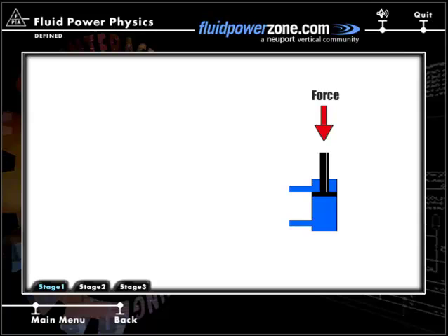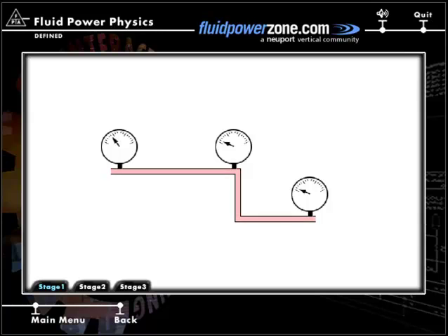This resistance to flow is load induced from the actuator, and also generated as the fluid is passed through the various conductors and components. All points of resistance, such as long runs of pipe, elbows, and various components, are cumulative in series and contribute to total system pressure.